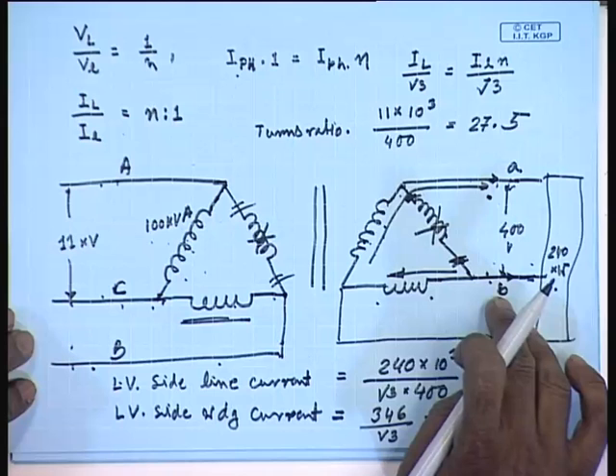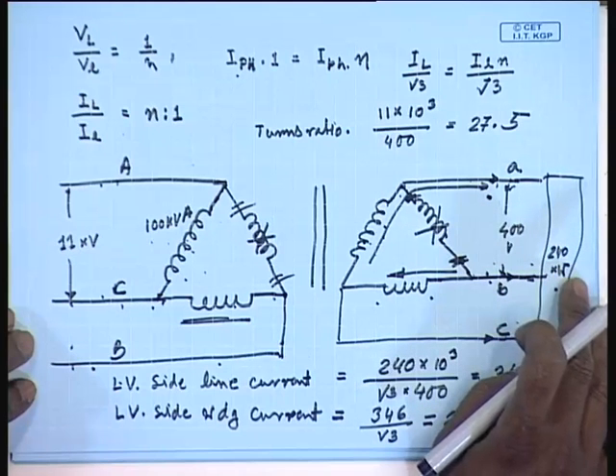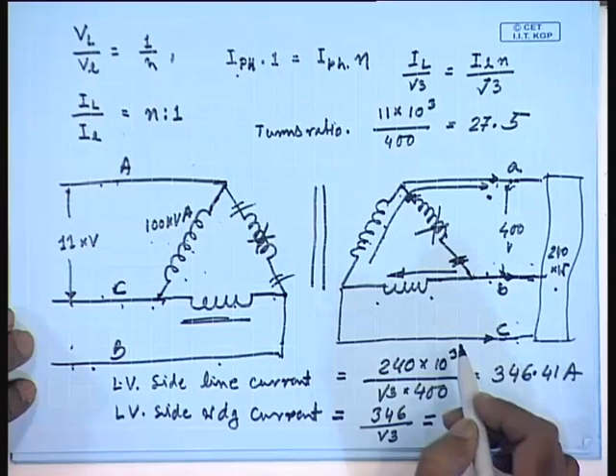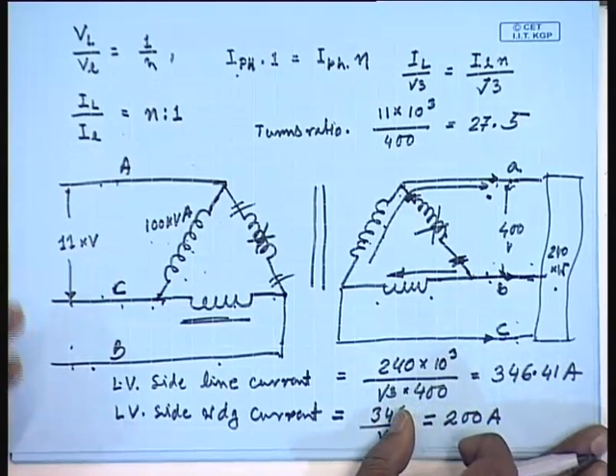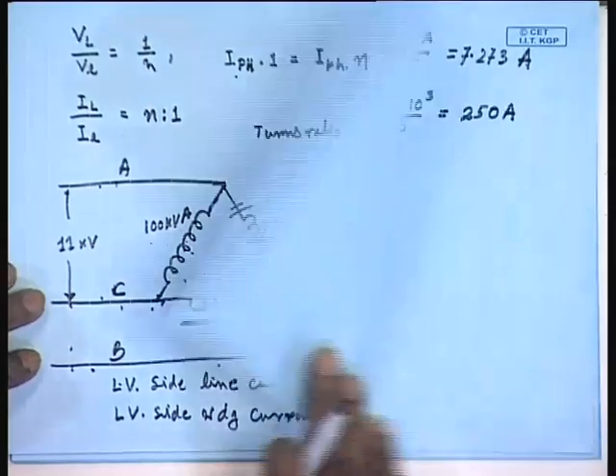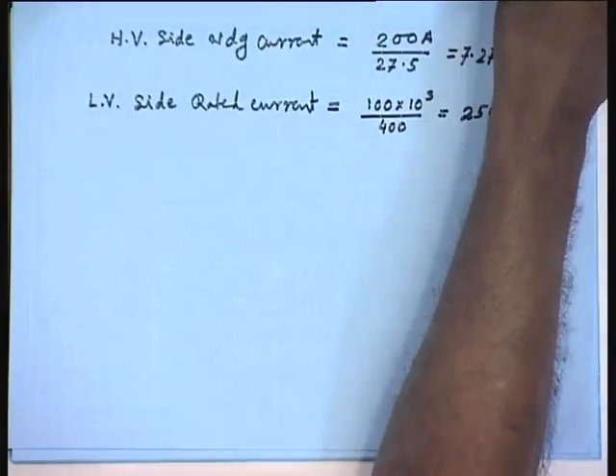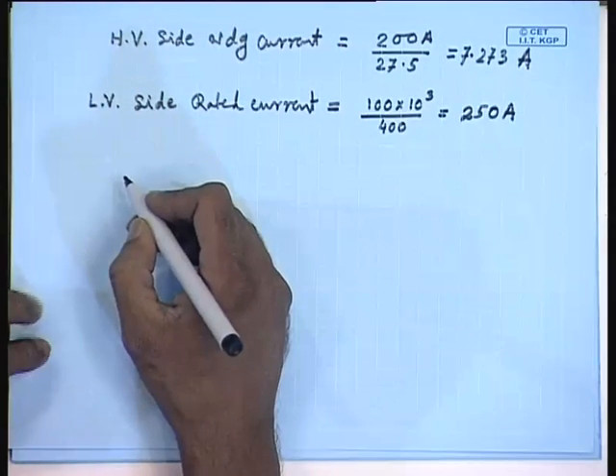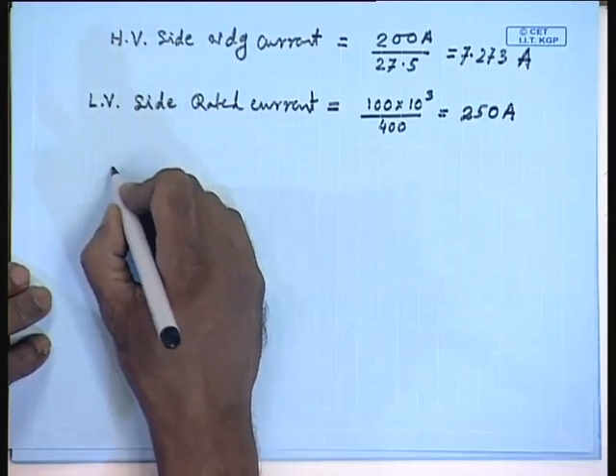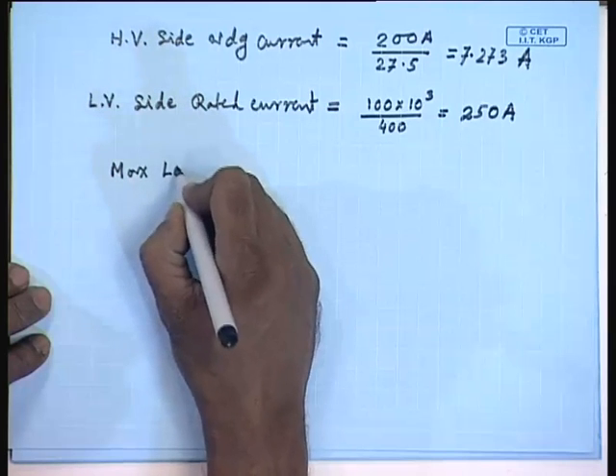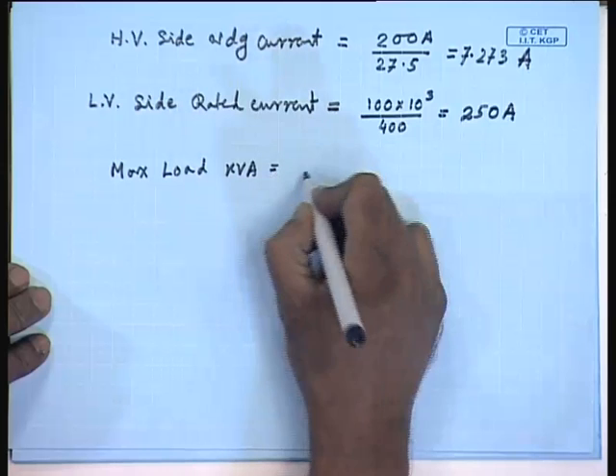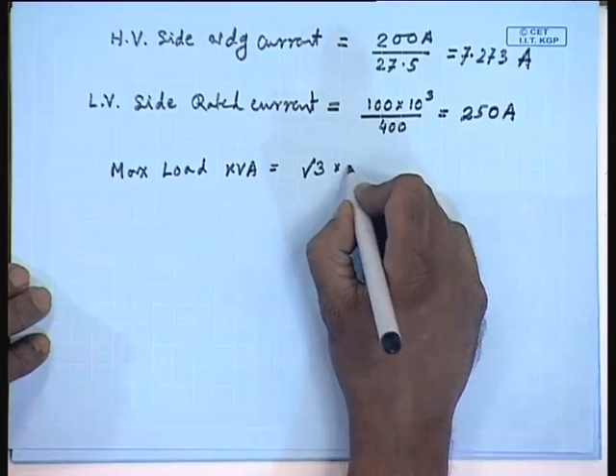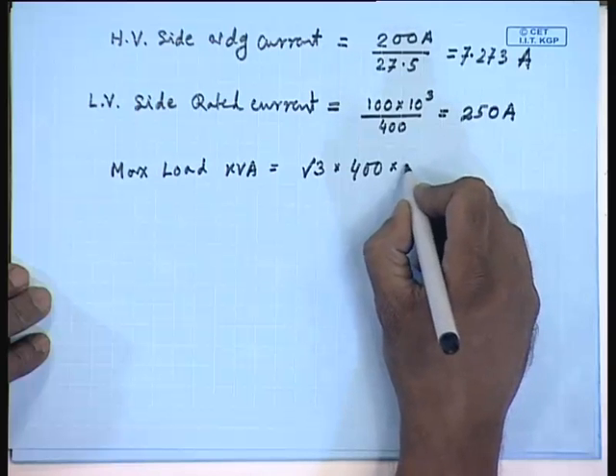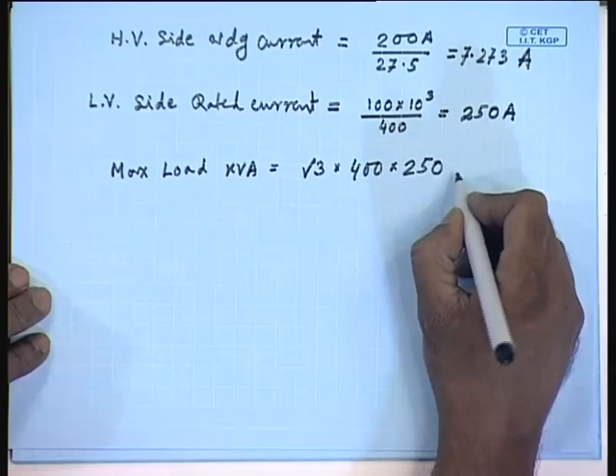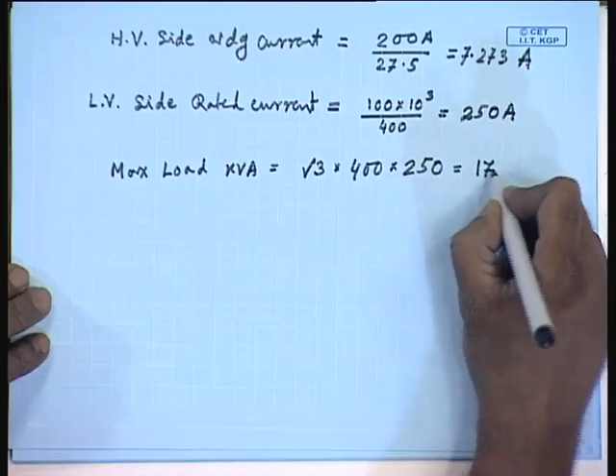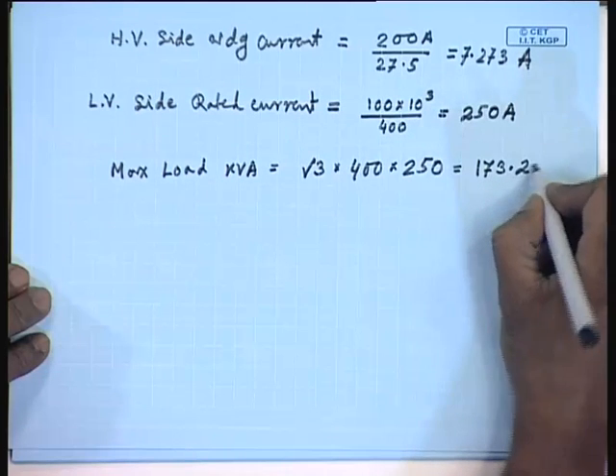Now, if this balanced line voltage supplies a balanced three phase load, the line currents will also be balanced. Hence, with open delta connection we have seen that the transformer will be able to supply a balanced 250 amperes of current. Hence, the total power that it will be able to supply, the maximum load kilowatt or load kVA, should be equal to root 3 into 400 into 250 amperes, which is about 173.2 kVA.